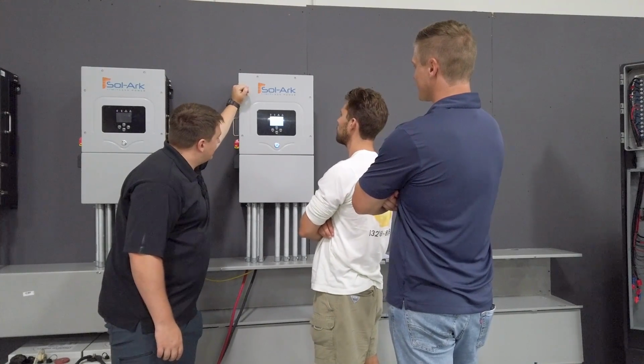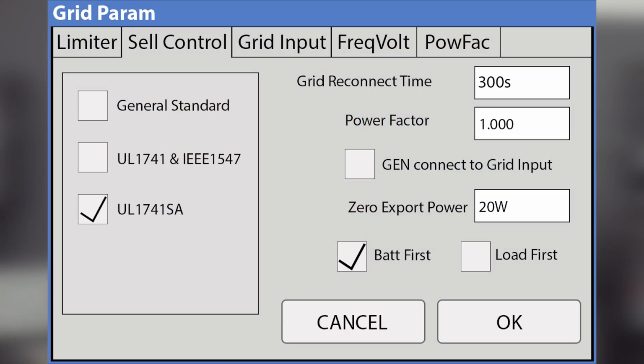Sell Control, as a general commissioning video, you usually don't have to change much, if anything, in here. Usually you'll leave it in UL 1741 SA mode, and battery first is going to be default, and I think appropriate for the vast majority of installs. If you do have a generator and you're using it on the grid input breaker, you do need to select this setting here, gen connected to grid input. That way we know to look for a generator, because obviously you can't sell back to a generator. It's going to be different than the grid, so we need to know if that's a possibility. So if you do have one of those, just go ahead and select that.